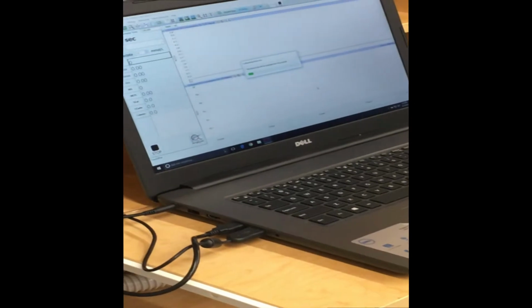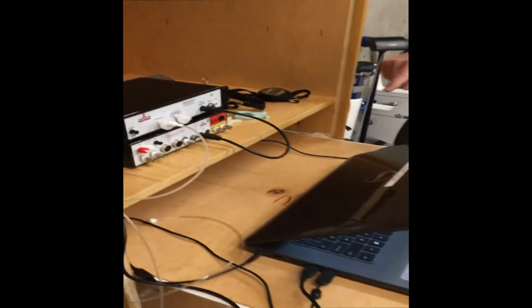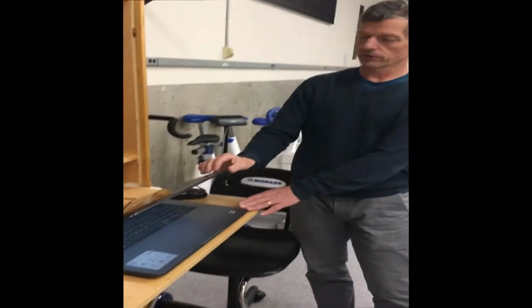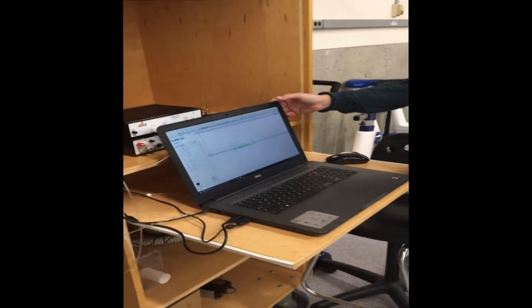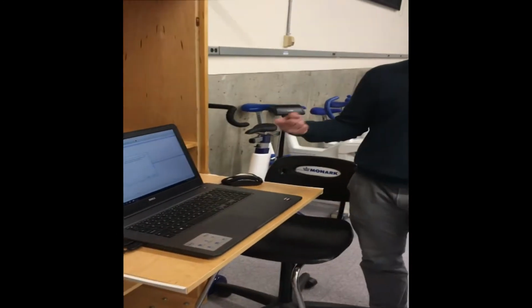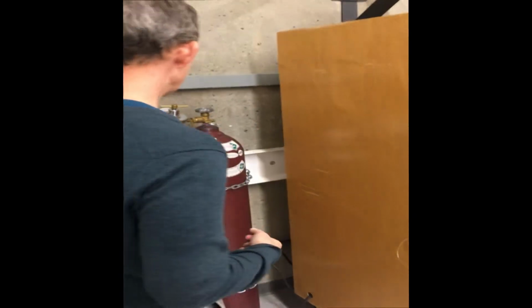Now what it's doing, it is sampling room air. So right now room air is going in there and it is sampling what the oxygen and CO2 concentration is of the room air. Now it's saying it wants to calibrate using the calibration gas, so it's telling us to open up the calibration gas.